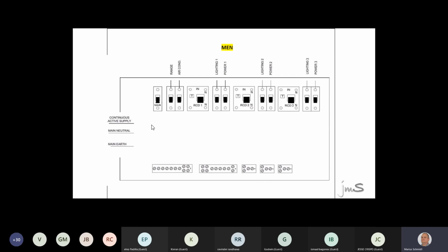Right, this switchboard. Do you all agree that the main earth, your main neutral, and your MEN link has got 2 screws? Right, it says that. But it also says a little other thing, that if the screw which goes in the hole covers the hole more than 80%, then it only needs 1 screw. So you can go and read that before you go to bed one night. That's more a regulation question. But my question is, do we put a tag in the switchboard? Yes. If you find that in the 3000 book, I'll buy you a Blue Label whiskey.